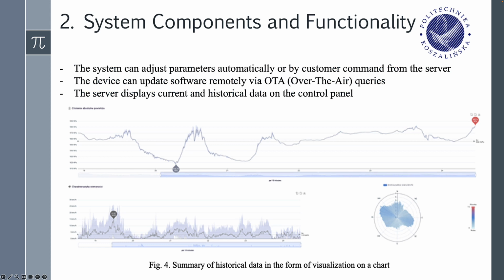The software also provides the possibility of remote updates, OTA, over the air. The device periodically queries the server, and if a new software version is available, it downloads the update file. Then, at a convenient time, the processors are switched to bootloader mode, and the update is carried out. Thanks to this functionality, the device fully fits into the concept of the Internet of Things, allowing for fully remote management of the system and introducing any changes to the software without the need for hardware intervention. The data aggregated on the server in the database is presented on the control panel, see Figure 4, divided into sections of current measurement data and a summary of historical data in the form of visualization on the chart.